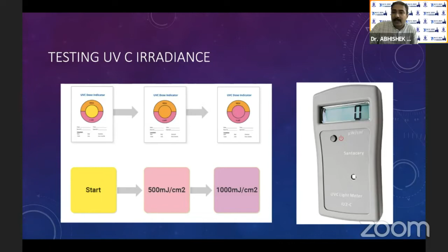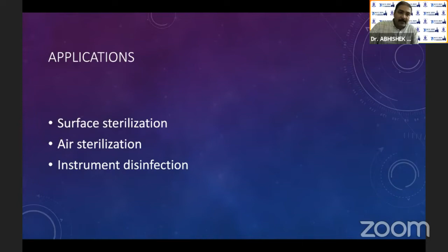You also have these meters, dosimeters. I don't think we need to buy it because we don't use it that much. But if you really want to test every corner of a room, you can have these UVC light meters which tell you exactly the microwatt per centimeter square that is landing on the particular area. Now we have three applications in healthcare where we currently use UV light: surface sterilization, air sterilization, and instrument disinfection. For surface disinfection, you have a wide range, from the micro USB attachable attachment that I'm showing to mobile and portable devices, to huge devices which you can shift from room to room.